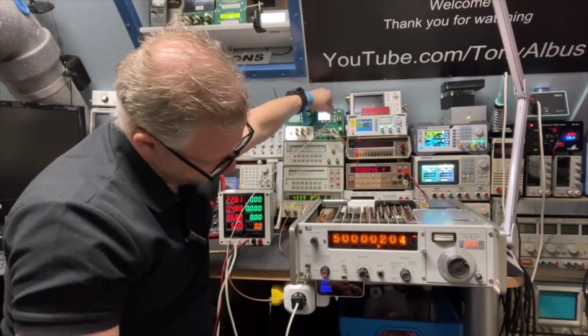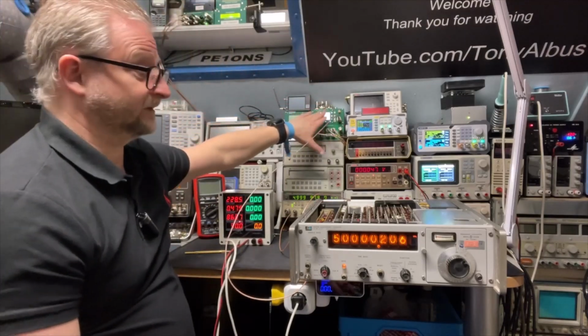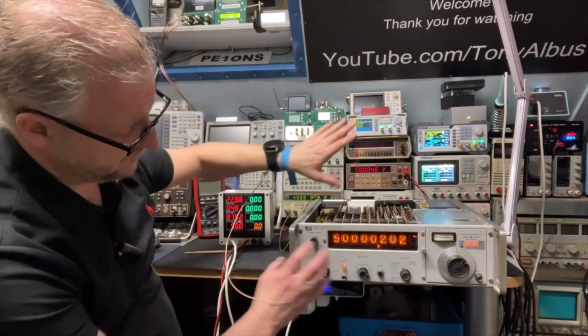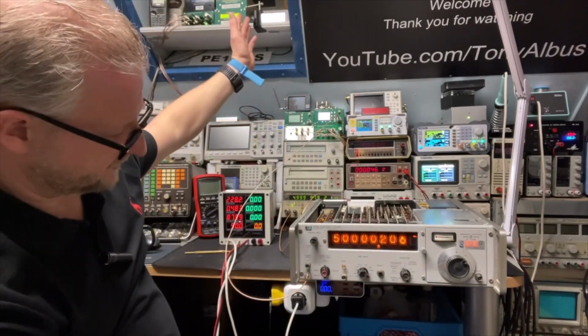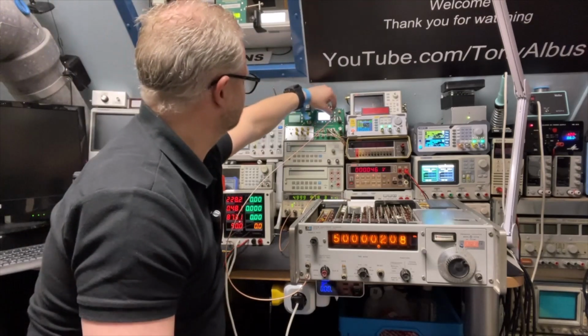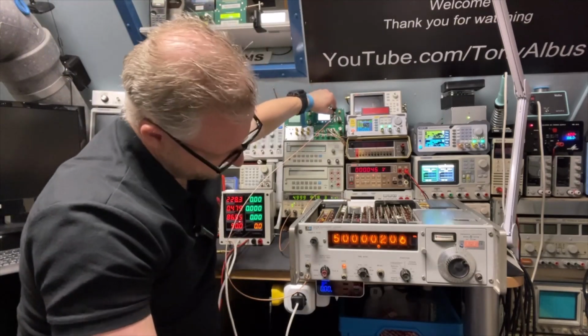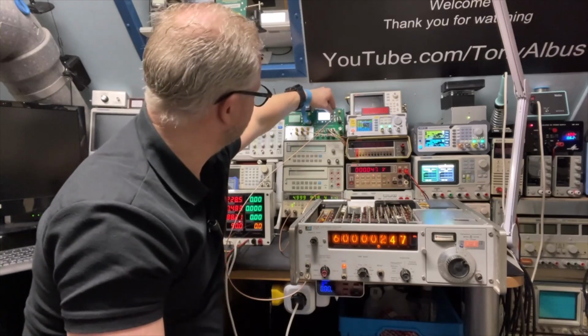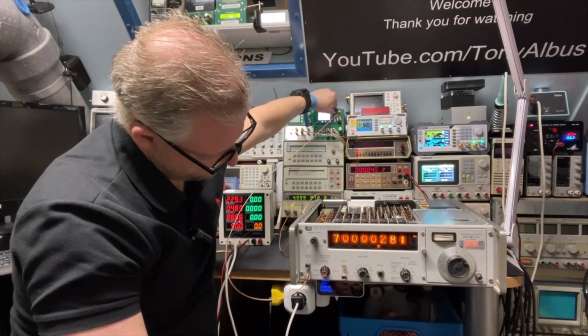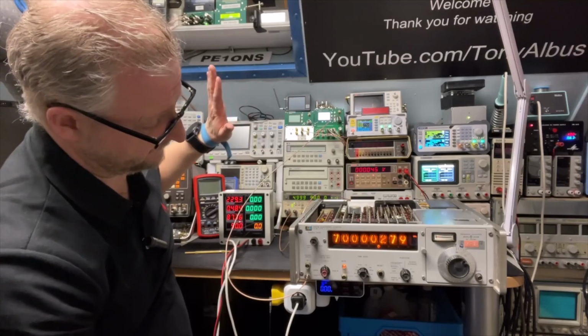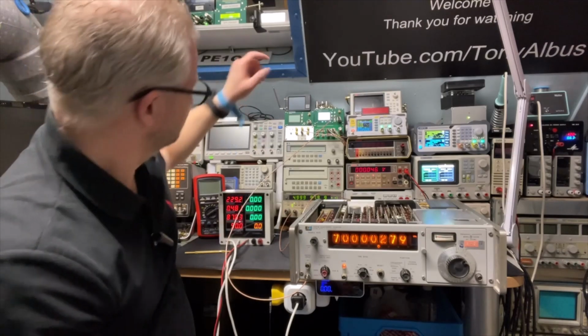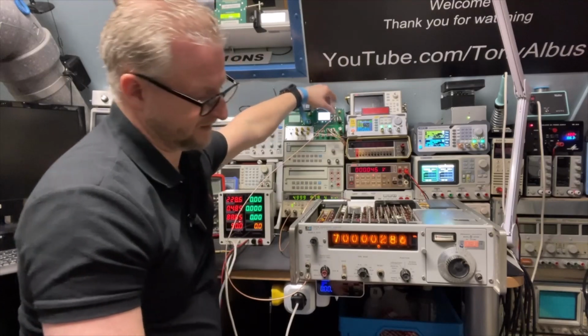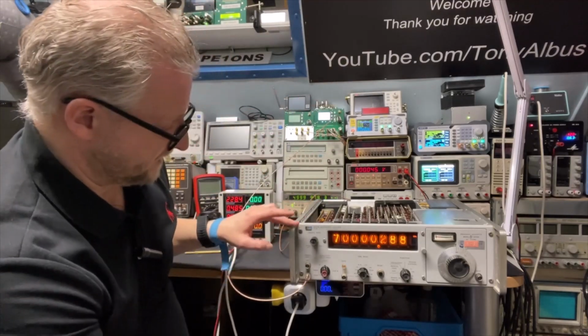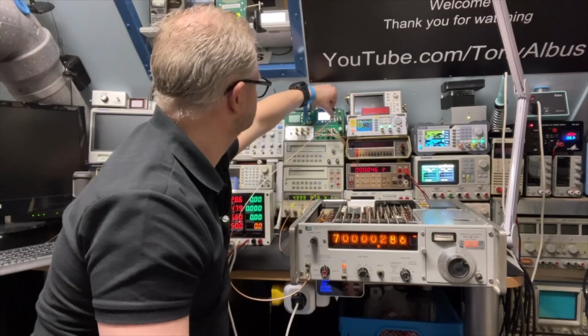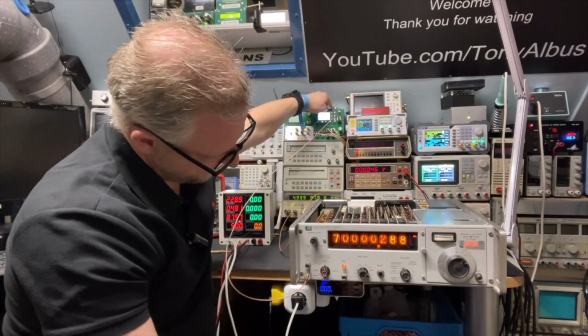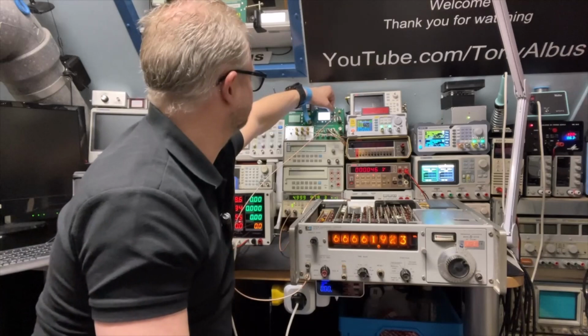And this one is also connected to external reference, so that's why it is still a little bit off. Let's go to 60. Can it do 60? It can. Can it do 70? It can. And it's sort of a stable reading still. Can it go a lot higher than 70? Because it is spec'd for 50. No, it doesn't do 80.